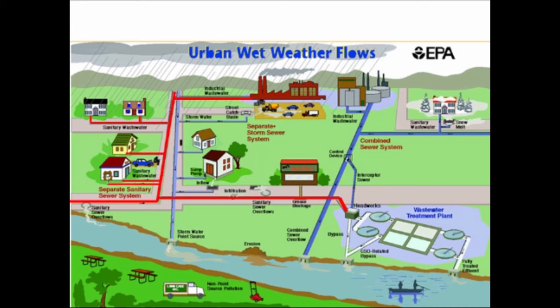On this picture, the lighter blue lines coming from the industrial and street areas show the stormwater system — a separate system from the sanitary sewer. Over on the far right of the screen, the darker blue shows a combined sewer system, in which both the sanitary sewer and stormwater flows into the same conduit. If there's an overflow of capacity, the excess bypasses the wastewater treatment plant and goes into the river.